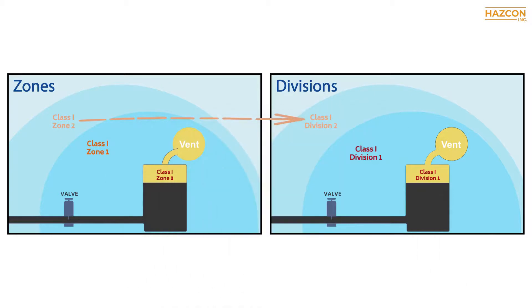And finally, zone 2 products may be installed in Division 2. They may not be installed in Division 1, zone 0, and zone 1.